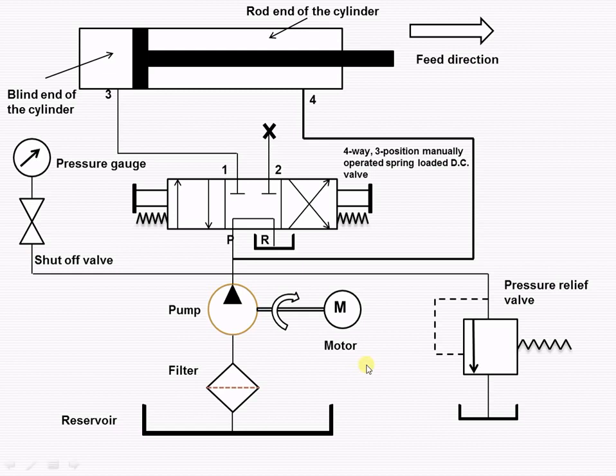This figure shows a regenerative hydraulic circuit which is used to speed up the operation of the cylinder during its outstroke. It uses a three-position four-way direction control valve with its port blocked, and the lines to both ends of the cylinder are connected in parallel, as shown here.